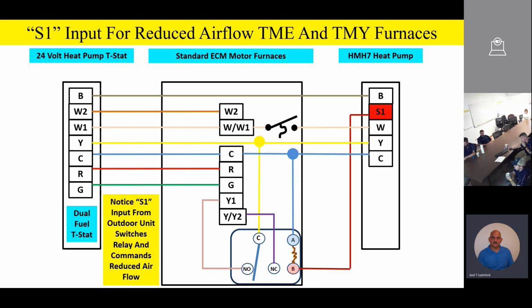That's the sole purpose of that: to prevent the furnace from short cycling every time we get a heating call, because the heat pump outside is designed to bring on the auxiliary heat for about a minute to kind of warm the air up a little bit. The whole idea being that it warms the air up before the heat pump comes up to full speed. It's a comfort thing. It's strictly a comfort thing.